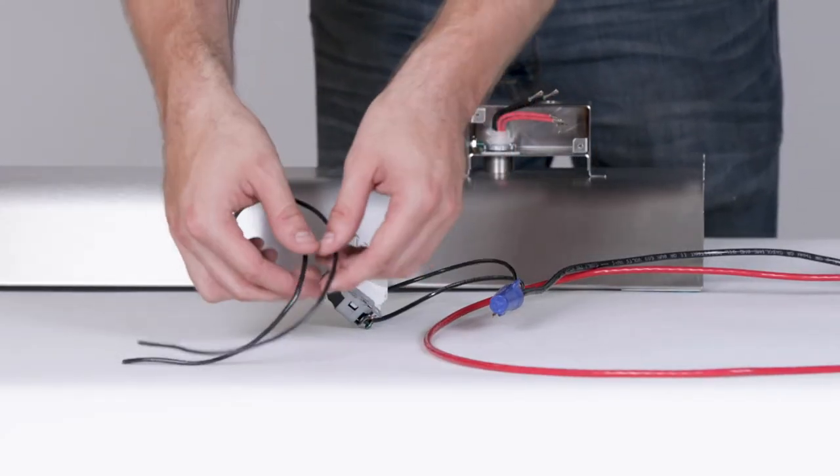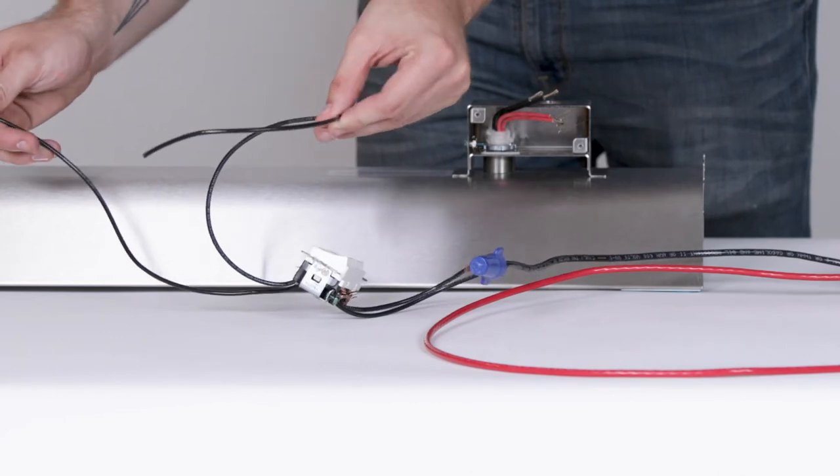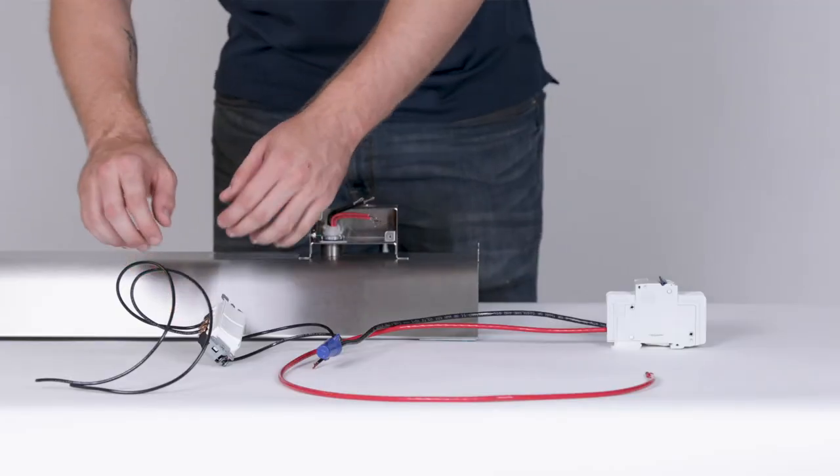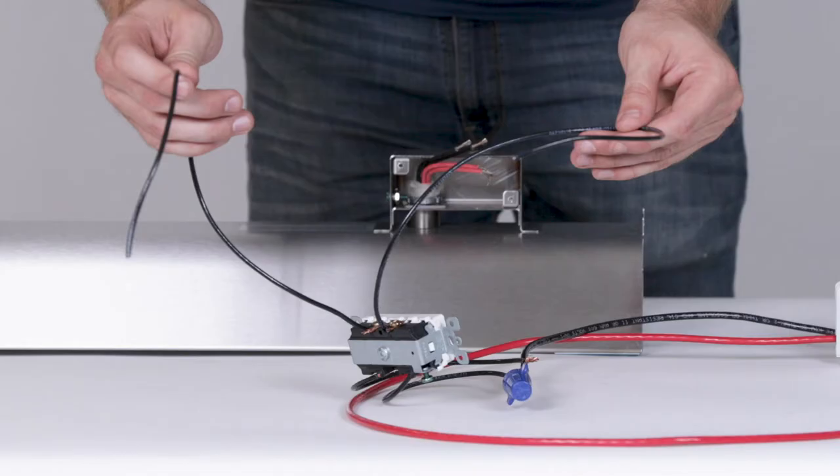We recommend using 12 gauge wire when tapping conductors that are 10 gauge or larger. We've provided a large blue wire nut to aid in this process. Now that we've taken care of the switch input, we'll be referring to the output of the switch as line 1A and line 1B.